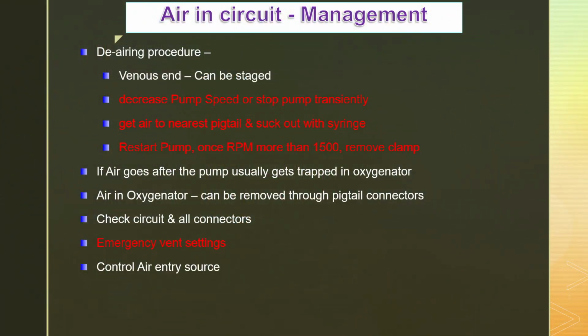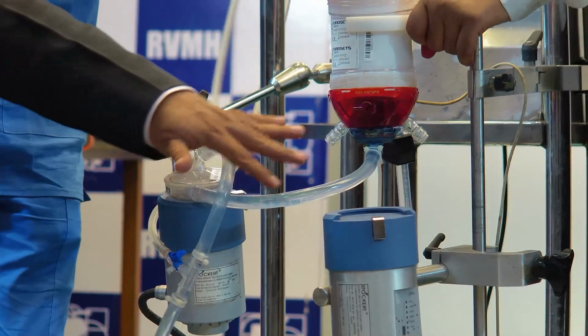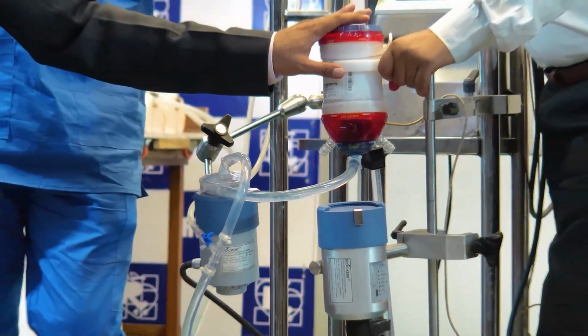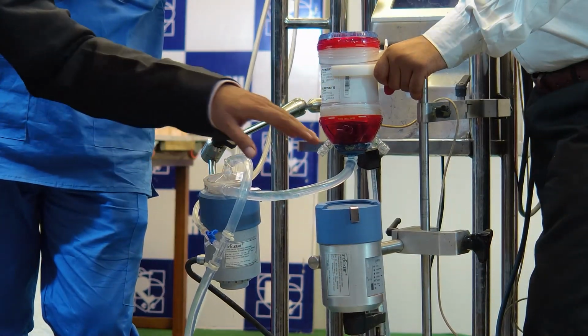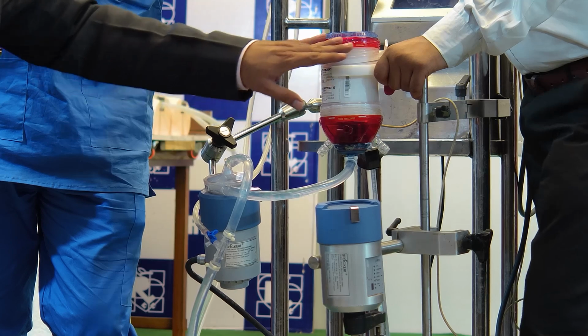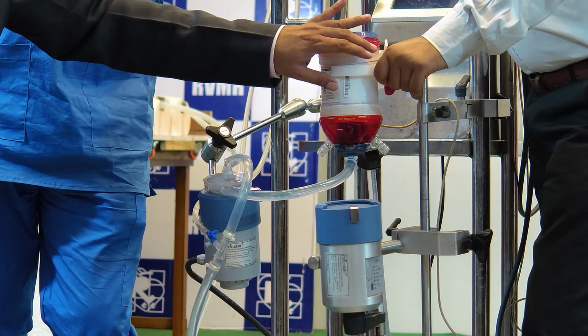So it won't cross the pump. Even if it does cross the pump, the oxygenator is going to trap it, so you are not worried about that part. You can do it in two or three steps and remove the air from the pump like this. If it goes to the oxygenator, you don't require to do much, because it will get trapped there and come up somewhere in the oxygenator upside.